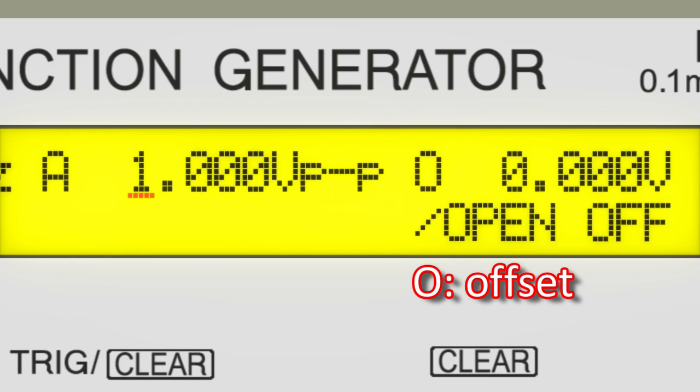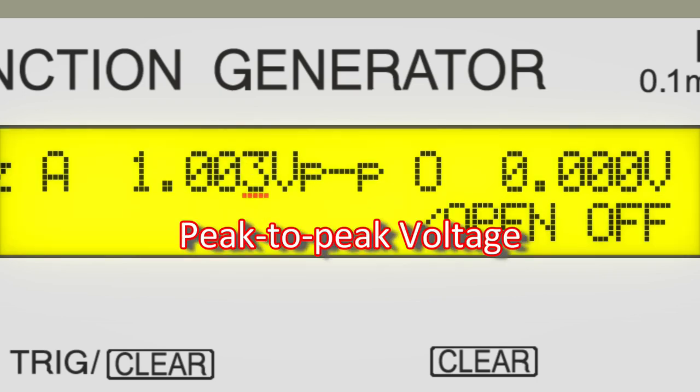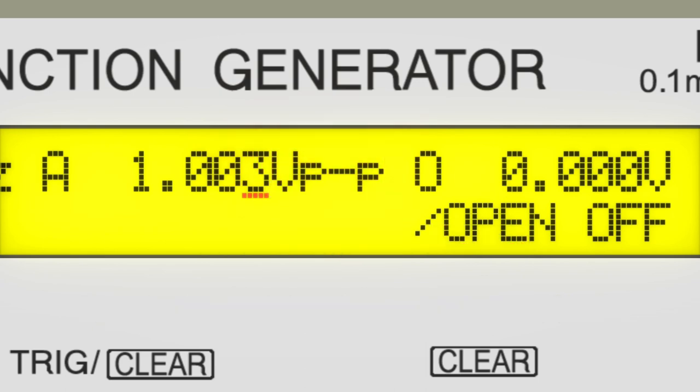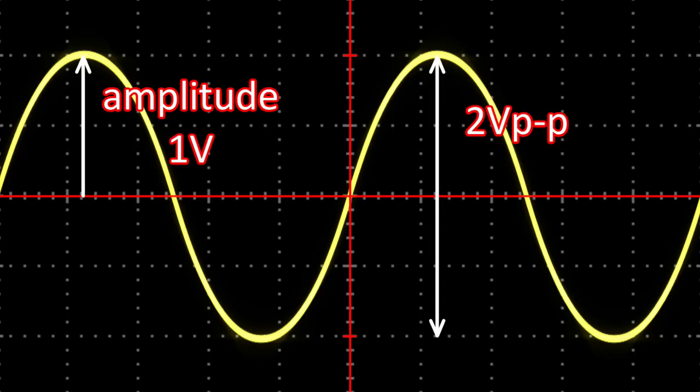As with frequency, use the arrow keys to move the cursor left and right, and use the Modify dial to move the value up or down. The unit VPP refers to peak-to-peak voltage, or the difference between the maximum and minimum values of a voltage waveform. Note that this is different from the amplitude used in natural science. 1 volt amplitude of sine wave AC corresponds to 2 volts peak-to-peak.